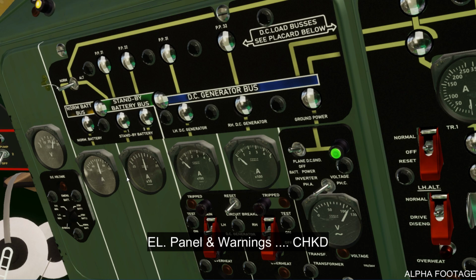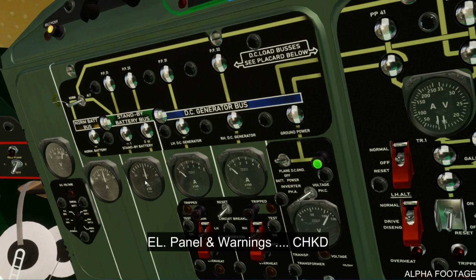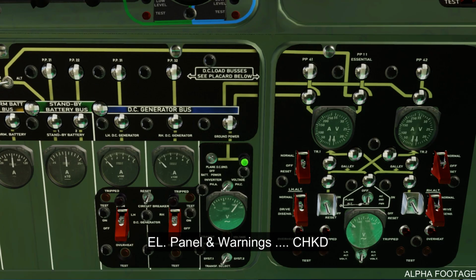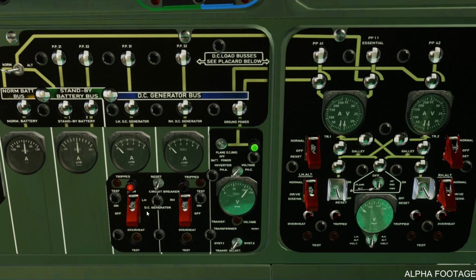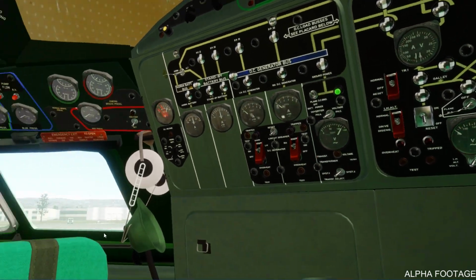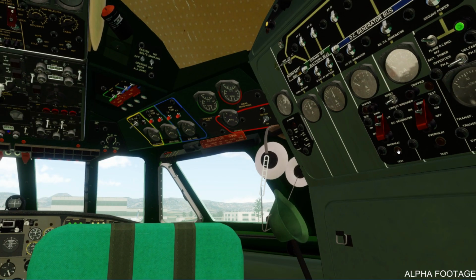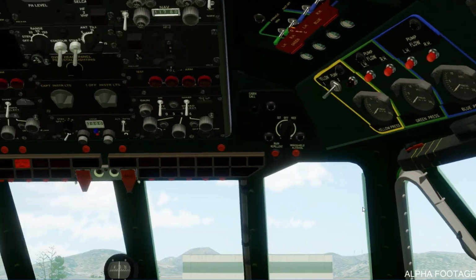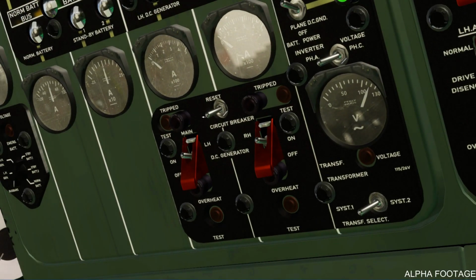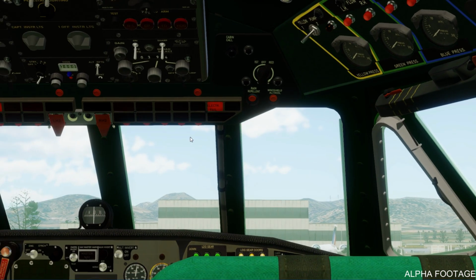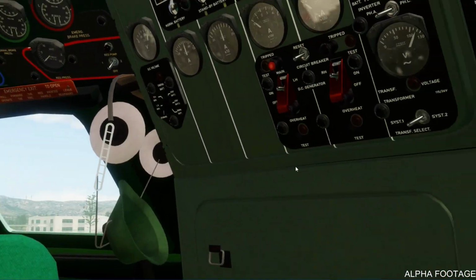Check that the emergency power selector is safety wired in position norm. Test the generator and alternator trip and overheat warnings. Okay, so we trip and reset, and we trip and reset. And now correctly, the overheat will no longer trip the generators. Oh, and by the way, I didn't show you. If you press an overheat or a trip, you will get the electrical fail master warning as well.